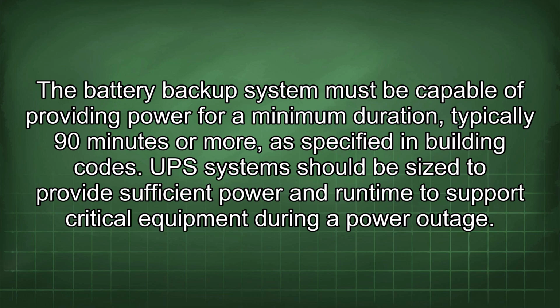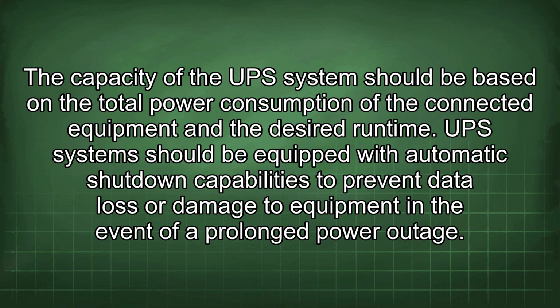UPS systems should be sized to provide sufficient power and runtime to support critical equipment during a power outage. The capacity of the UPS system should be based on the total power consumption of the connected equipment and the desired runtime. UPS systems should be equipped with automatic shutdown capabilities to prevent data loss or damage to equipment in the event of a prolonged power outage.